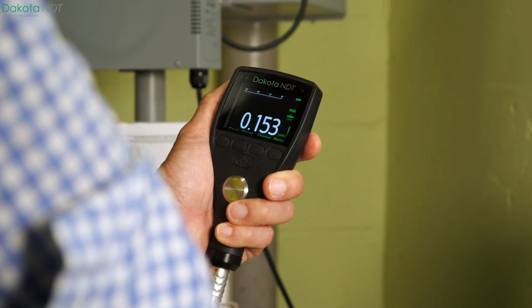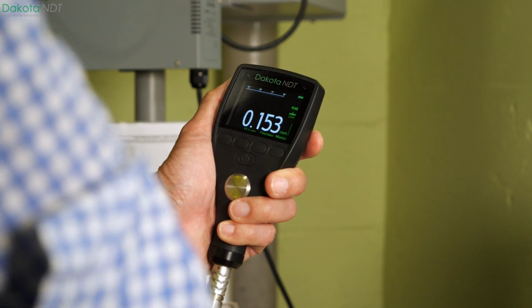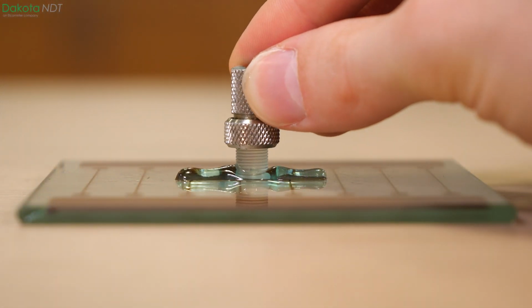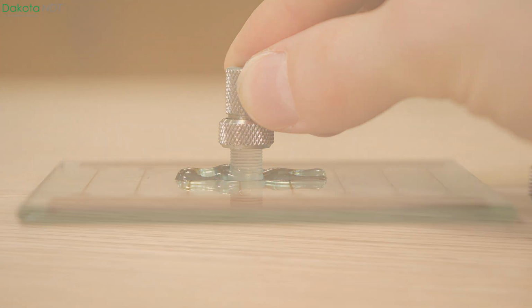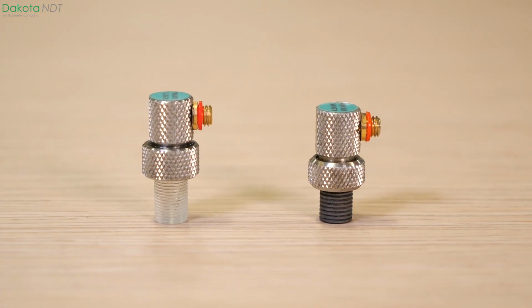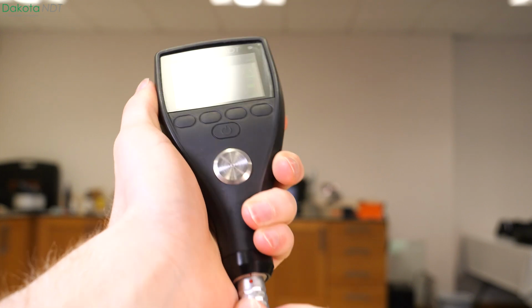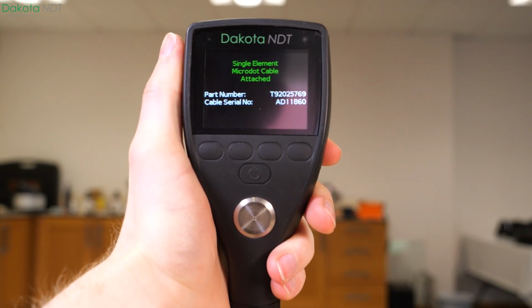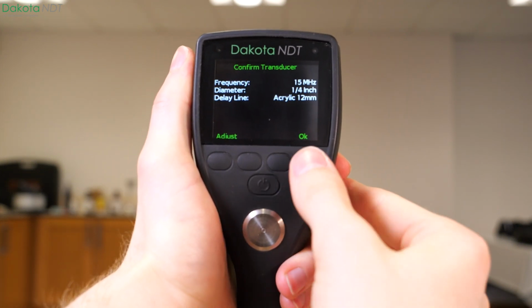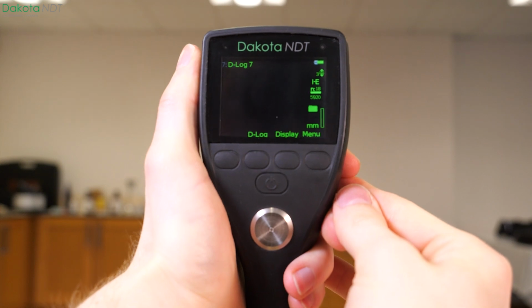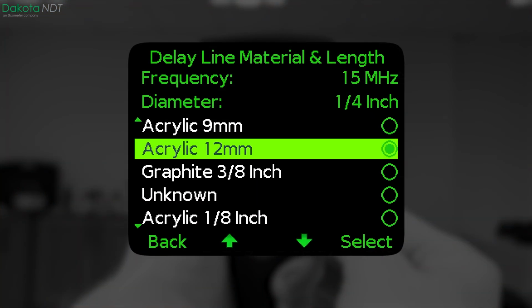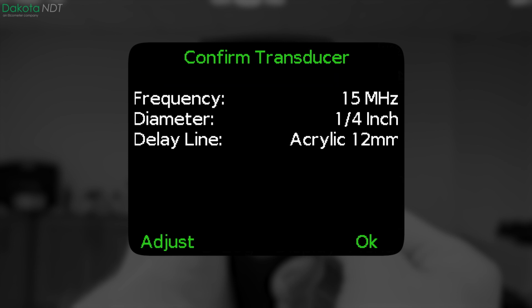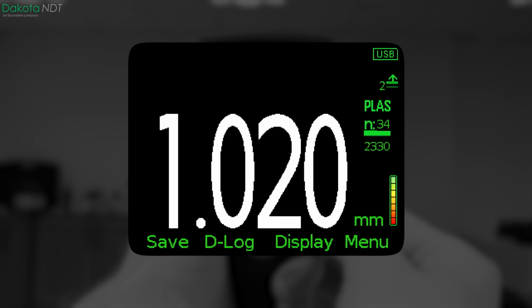The DakotaNDT PCX thickness gauges are designed to work with DakotaNDT's range of intelligent transducers, which all have automatic probe recognition. As soon as the transducer is connected to a gauge, it immediately detects what type of transducer you're working with. All you need to do is set the appropriate length and material of the delay line and input the frequency and diameter of the transducer.